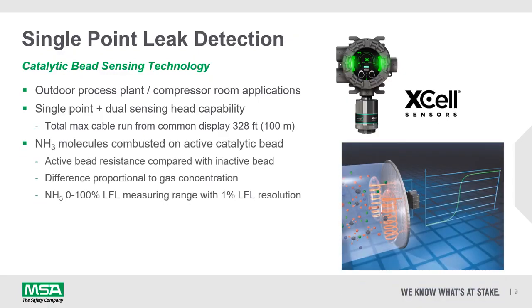They work on the principle that the ammonia molecules, when diffused into the sensor head, combust on the surface of an active catalytic bead. This combustion changes the resistance of that active bead and is then compared with the resistance of an inactive bead, the difference being proportional to gas concentration. But this technology is typically used for ammonia at the explosive level.